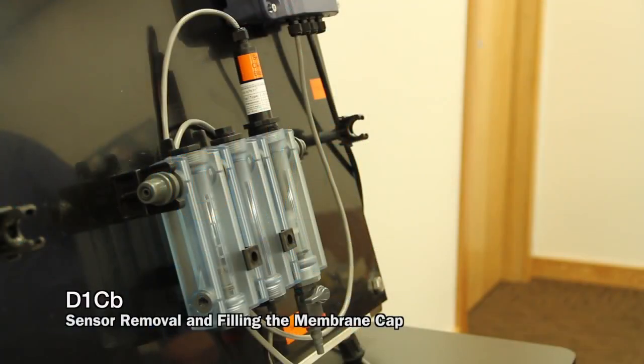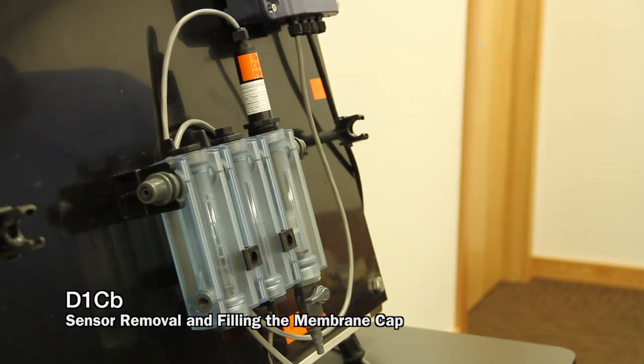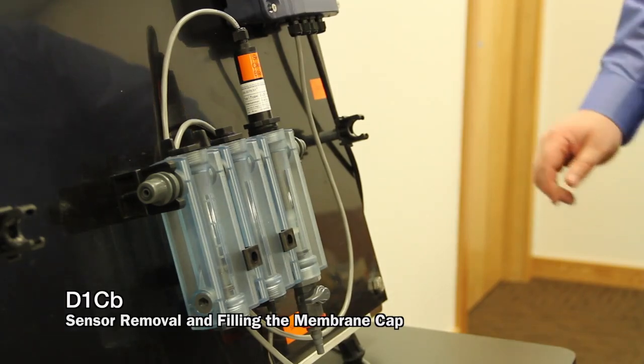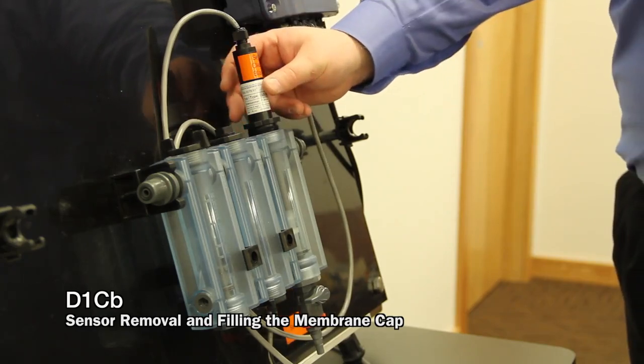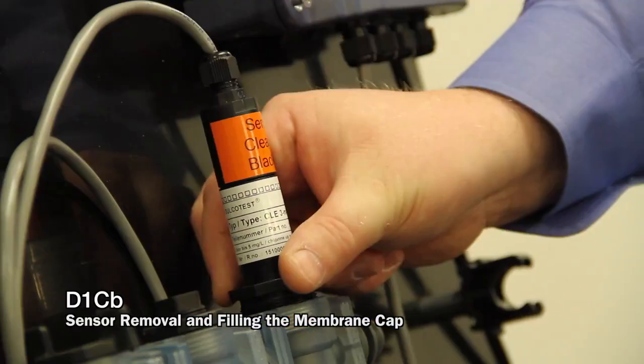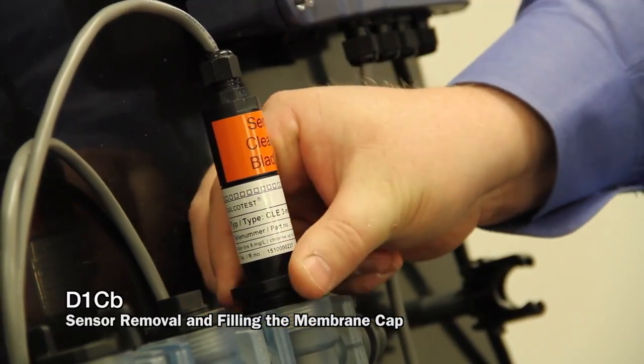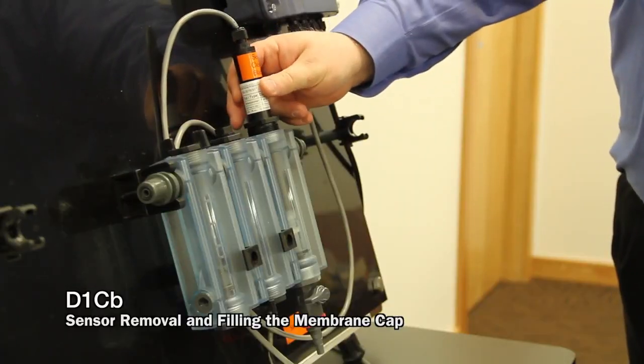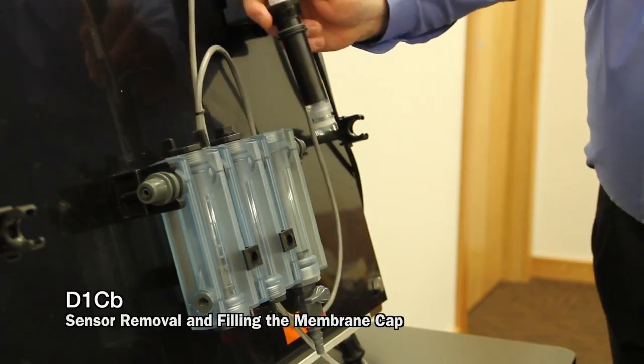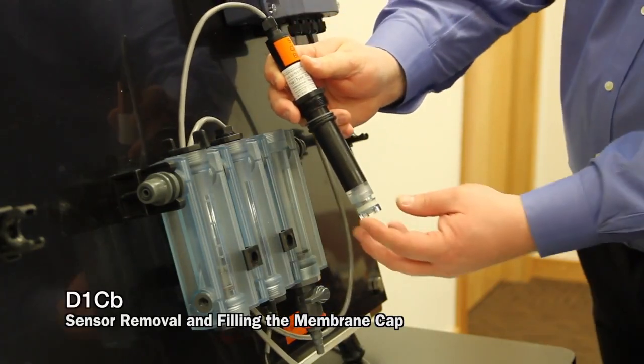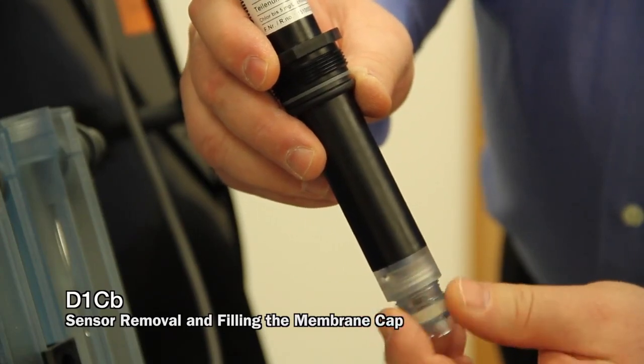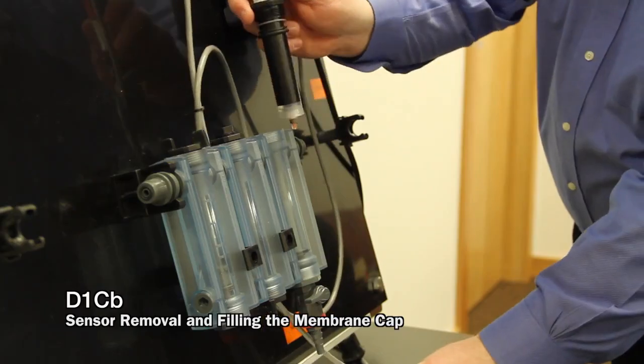This section is to show removing the sensor from the sample line and filling the membrane cap with electrolyte. So we're going to be sure that we don't have flow in our sample line. Loosen the compression fitting holding the sensor in place. Remove the sensor from its sample cell. Remove the membrane cap.